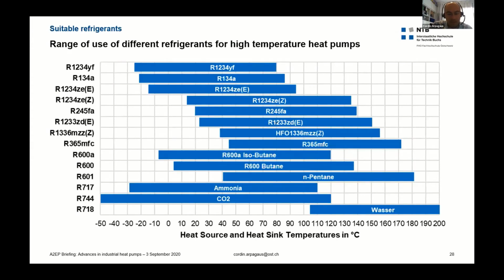So on this graph, I tried to summarize the most used refrigerants as a function of the heat source and heat sink temperature. You can see here, it starts at 0 degrees, goes up to 100 degrees, then 200 degrees. And at the highest temperatures, it's water. So water steam is the most efficient refrigerant. Then we have CO2, up to around 120 degrees because of the transcritical cycle. Then we have ammonia, which goes up to 110 degrees heat sink temperature. This is limited by the compressor maximum pressure, which is increasing. So 70 bar, for example, or more is possible today.